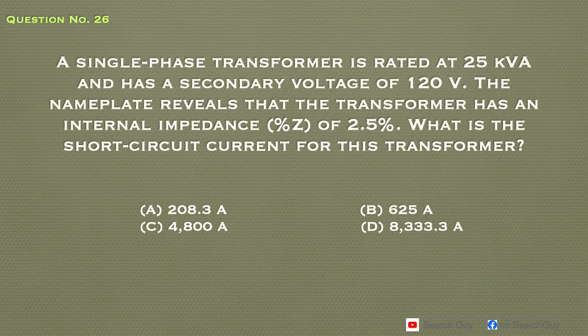Question number 26. A single-phase transformer is rated at 25 kVA and has a secondary voltage of 120 volts. The nameplate reveals that the transformer has an internal impedance %Z of 2.5%. What is the short circuit current for this transformer? A. 208.3 amperes, B. 625 amperes, C. 4,800 amperes, D. 8,333.3 amperes. Answer: D. 8,333.3 amperes.